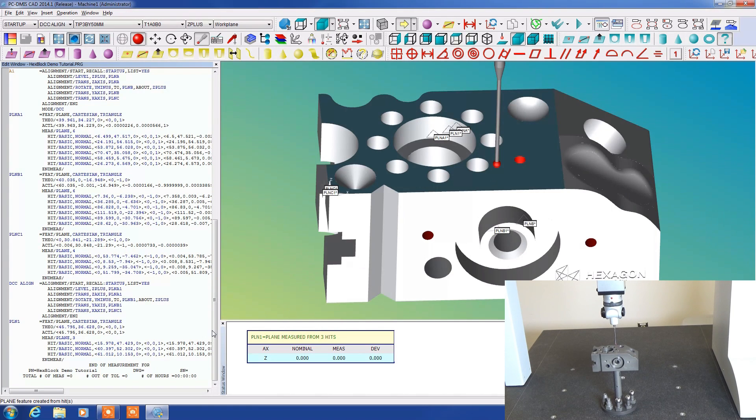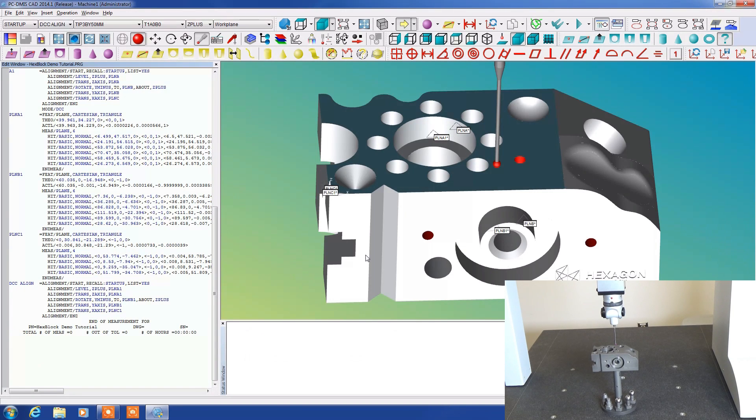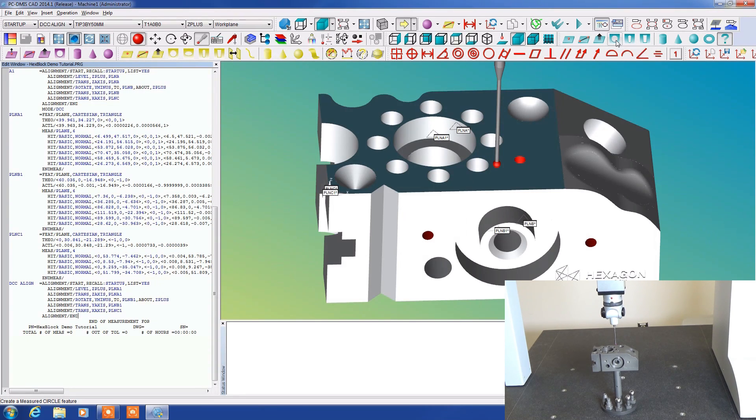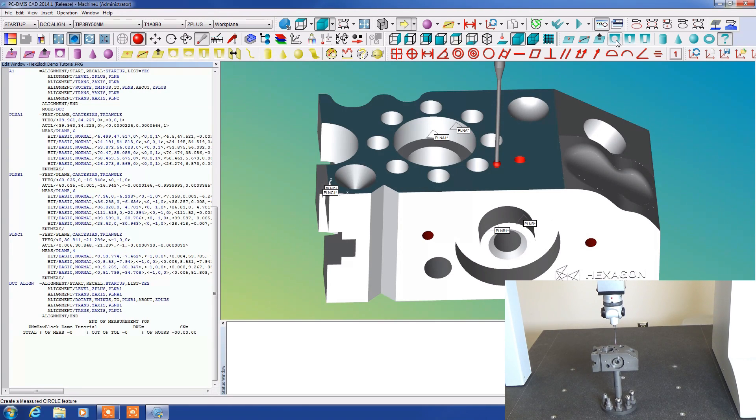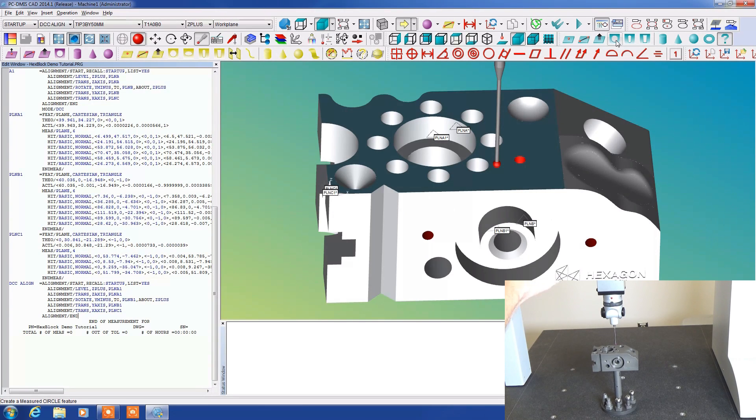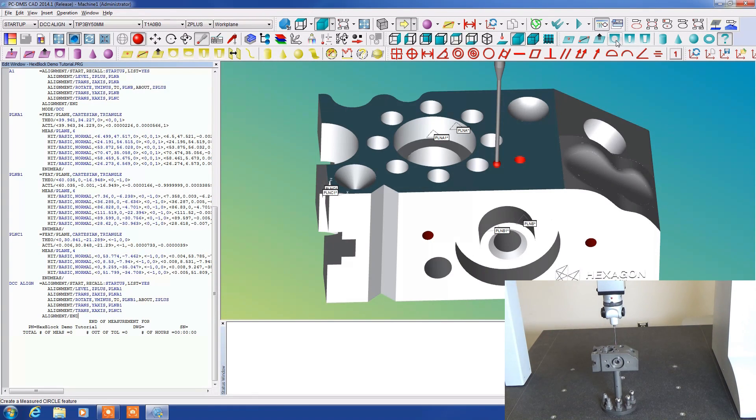These are just some of the many features we have here to work with. Let's talk about a few of these other measured features. Measured circle requires that you take a minimum of three points. However four or five points would certainly help it out more. They all need to be in the same plane. So you can't put two points in one plane and then the other one a little bit further down. It won't recognize that as a circle.